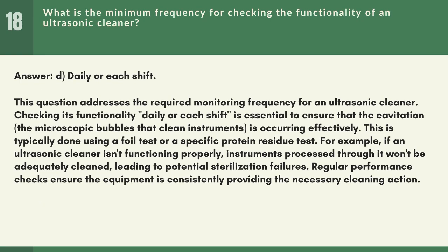Answer: D. Daily or each shift. This question addresses the required monitoring frequency for an ultrasonic cleaner. Checking its functionality daily or each shift is essential to ensure that the cavitation, the microscopic bubbles that clean instruments, is occurring effectively. This is typically done using a foil test or a specific protein residue test.